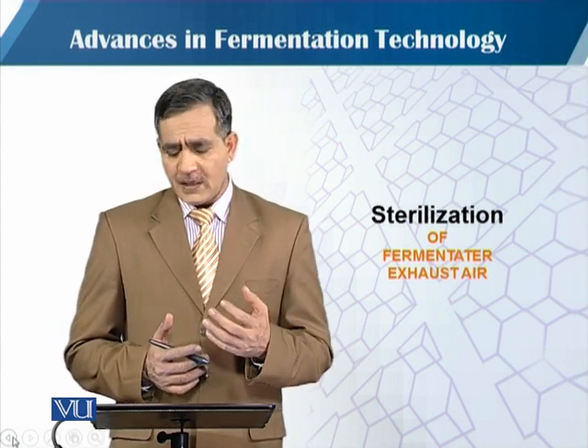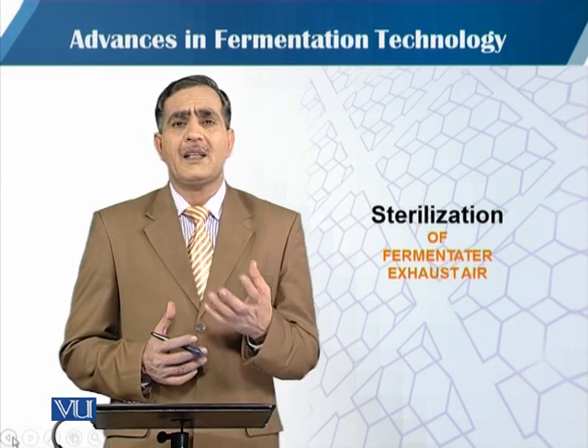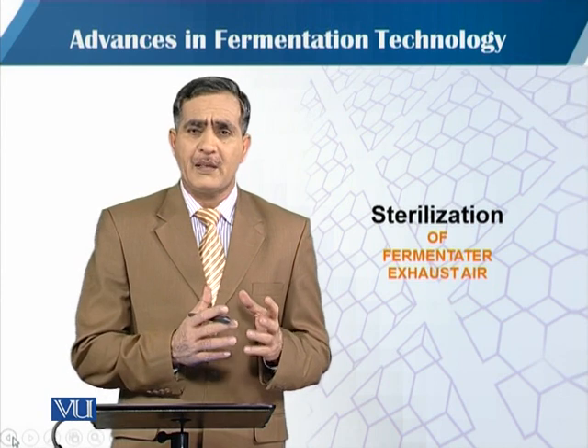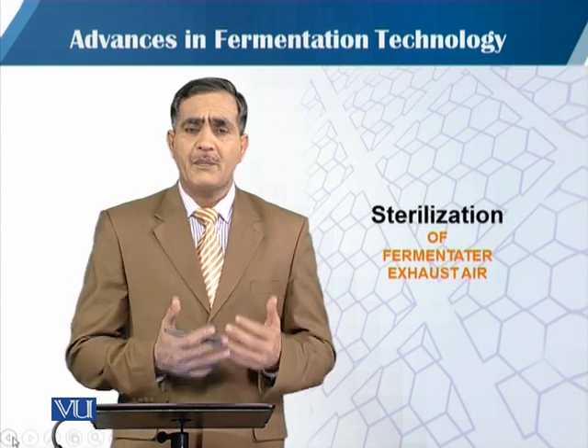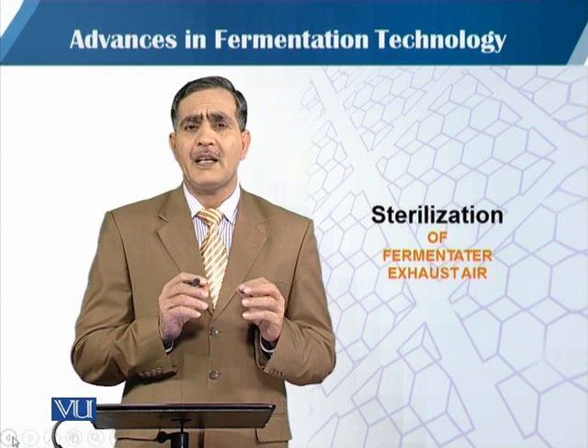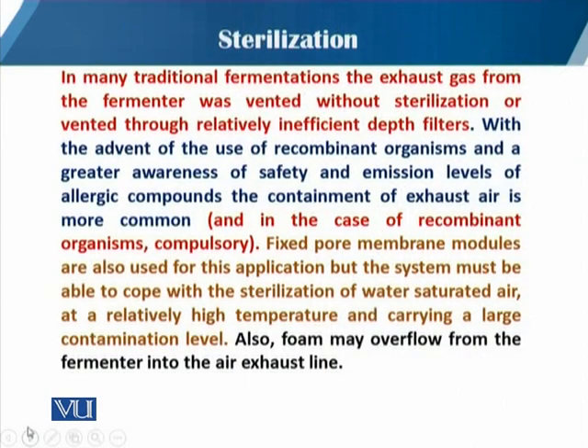When dealing with exhaust air, the problem is that the air is mostly wet, because when it passes through the fermentation medium it contains water vapors since the whole medium is liquid. In many traditional fermentations, the exhaust gas from the fermenter was vented without sterilization or through relatively inefficient depth filters.